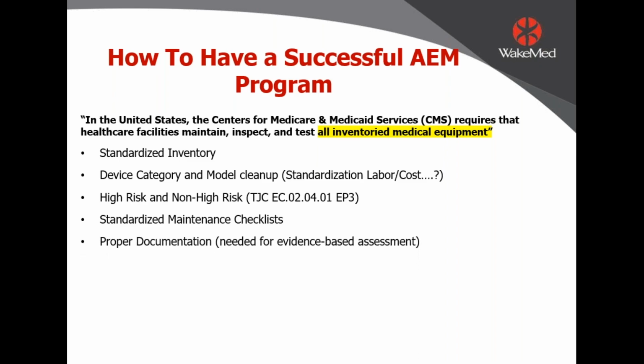Proper documentation. So in your CMMS, we always get it. The device comes down, or you get called up on the floor and it's broke, right? That's the description, broke. Well, you got to define it a little bit more than that, right? So you got to say what's broken, how did it break, get as much information into your documentation as possible. And then when you put in what you did to the device, tell a story, tell that repair story. Don't say fixed it and returned it to service. What did you do to fix it?